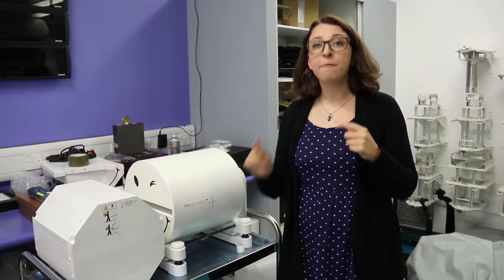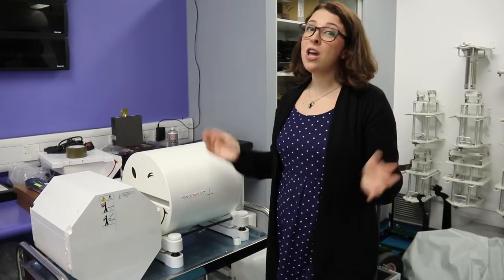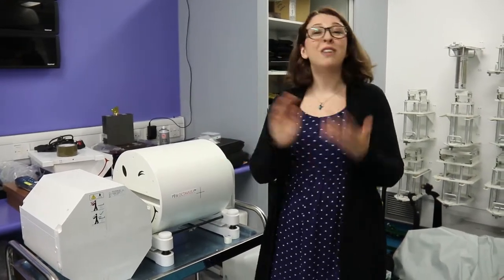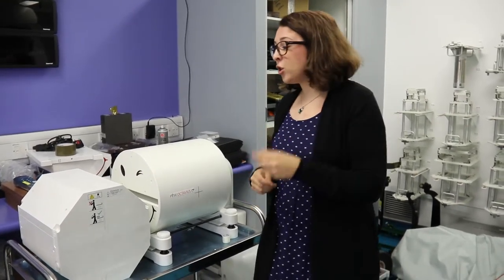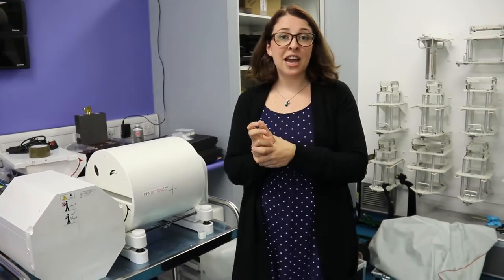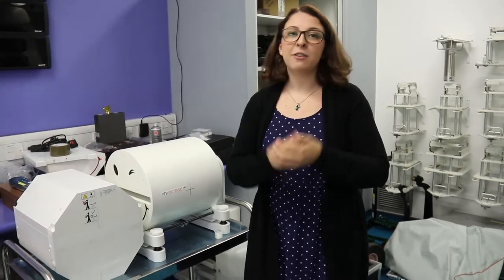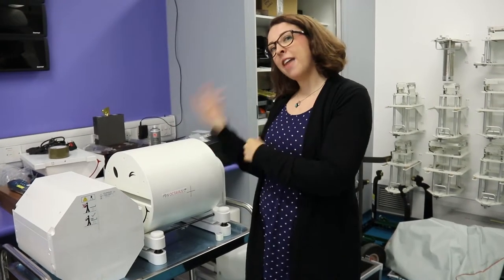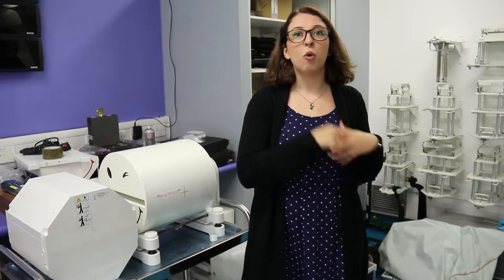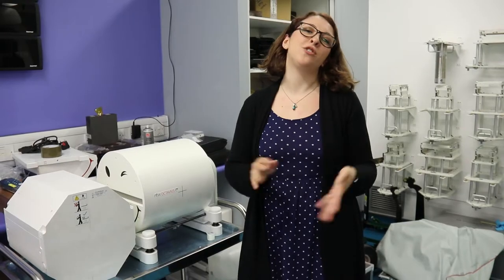What we do at NPL is we supply the basic calibration for LINACs to make sure that the hospitals around the country know what dose they're giving to their patients, because if you get the dose wrong, then you can receive too much or too little, both not very good. So what we do, we do different commissioning jobs, but we also do, people give us their chambers and we basically tell them exactly what current they receive under different radiation doses. And then they go back and they calibrate all of their dosimeters based on what we've told them. And this chain of events means that everybody's safe whenever they receive radiation treatment.